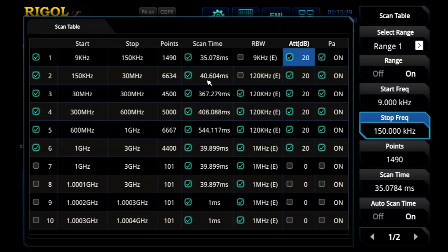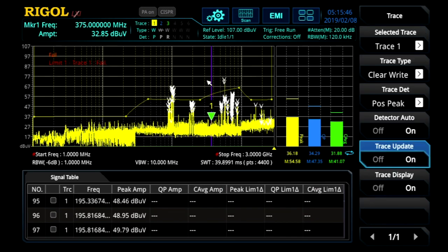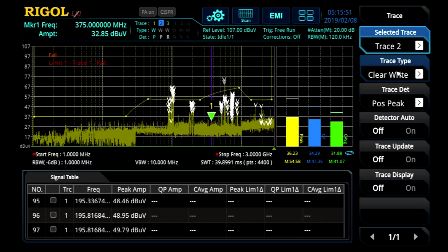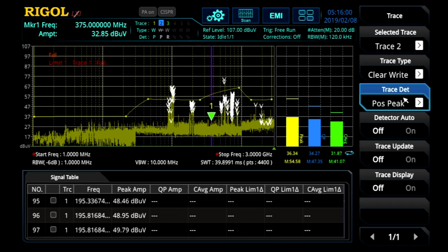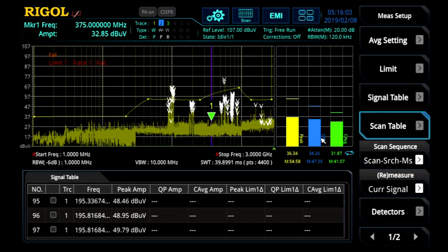Usually we let the scan time auto-set to what's required for that RBW setting over that span. We can also set the traces here. Here we're going to use one trace and use the positive peak, but additional traces are possible, including using quasi-peak and CISPR average detectors. In this mode, I like to use the peak measurement for a trace and then use all the detectors in measurement mode at the end.